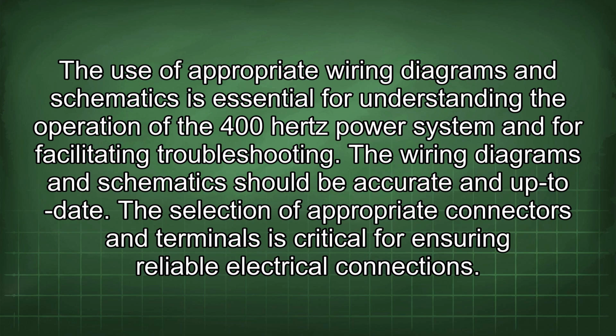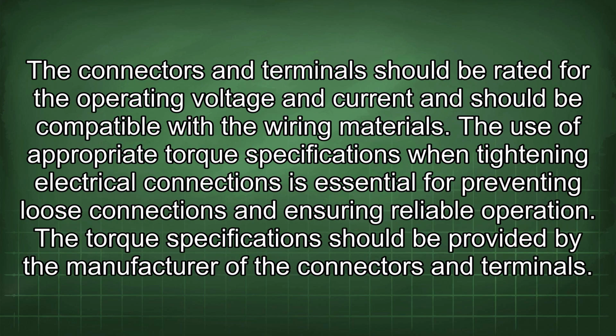The selection of appropriate connectors and terminals is critical for ensuring reliable electrical connections. The connectors and terminals should be rated for the operating voltage and current and should be compatible with the wiring materials. The use of appropriate torque specifications when tightening electrical connections is essential for preventing loose connections and ensuring reliable operation. The torque specification should be provided by the manufacturer of the connectors and terminals.